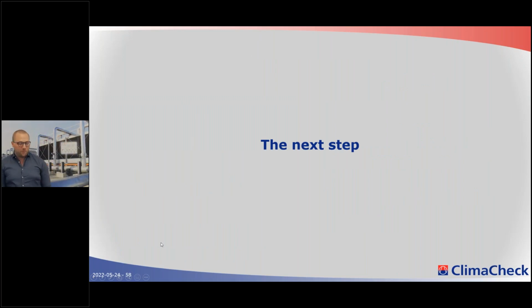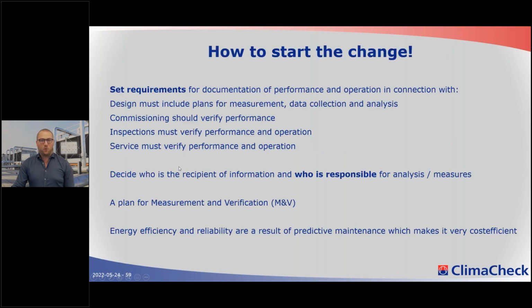So the next step, I mean, we see now that it's possible. The systems are there to analyze. There are the demands. It is with quite easy and cost-efficient measures that we can fix a lot of the problems that can be detected when you use, for example, the system efficiency index. Just for example, the case Rupen mentioned with the compressor that we saw during the commissioning. That system was just turned off when we were making sure that the values were corrected. So now it's up and running well, and you can see things very, very fast. But the next step, of course, is how to start the change. We can see now that it's so important to reduce power consumption, but we need to change.